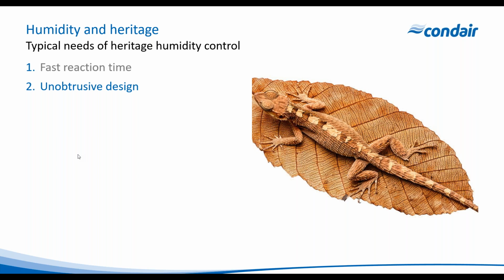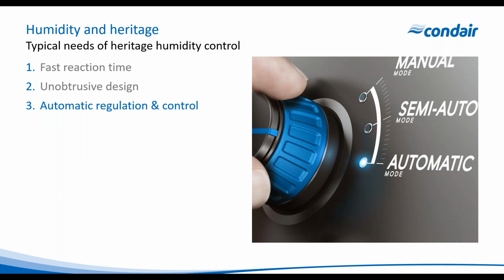So design can be critical, but not so easy, especially if you're in a listed building and there's no air delivery method. All of a sudden, you don't have any choice apart from to have a mobile unit actually inside the space. The humidifier or the dehumidifier must have automatic regulation. We've got to be able to have a set point that can be set, and the unit will sit and control its output according to the needs of the space.